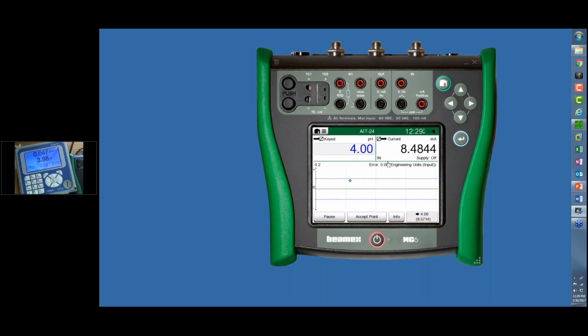Let me get that cable out of the way. So you're looking at my pH transmitter right now. So we're showing 3.98 pH. Now it's supposed to be 4. My tolerance on this pH happens to be 0.02. So it's within that uncertainty level. And we're also showing 8.55 milliamps on the transmitter. And you can see on my calibrator, we're actually showing 8.4843.